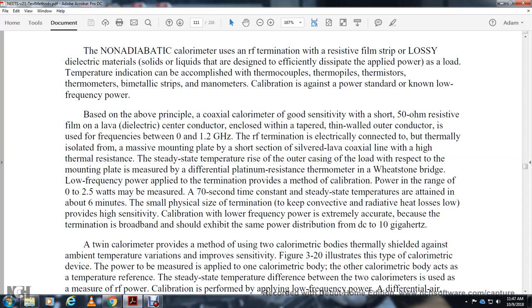Based on the above principle, the coaxial calorimeter is of good sensitivity with a short 50 ohm resistive film, with a dielectric center conductor and a thin-walled outer conductor, used at frequencies between 0 and 1.2 gigahertz. The radio frequency termination is electrically connected to, but thermally isolated from, the mounting plate with a short section of coaxial line with a high thermal resistance. The steady state temperature rise of the outer casing of the load with respect to the mounting plate is measured with a differential platinum resistance thermometer in a Wheatstone bridge.